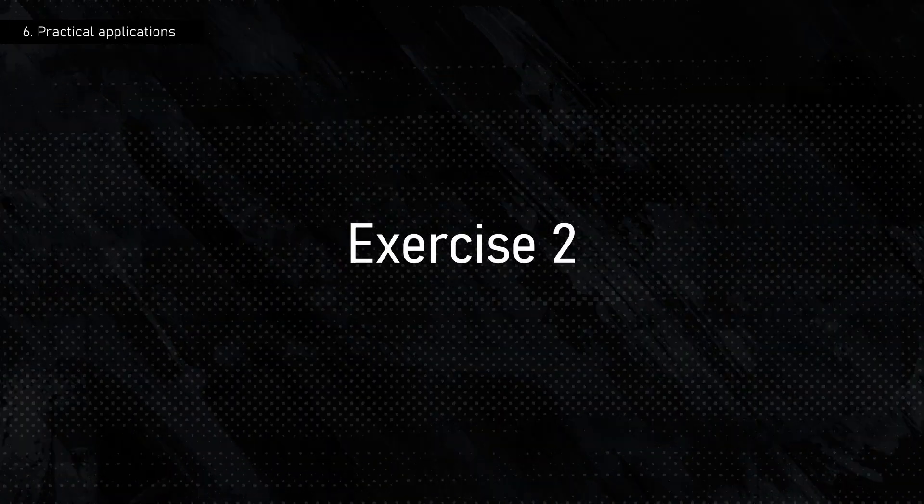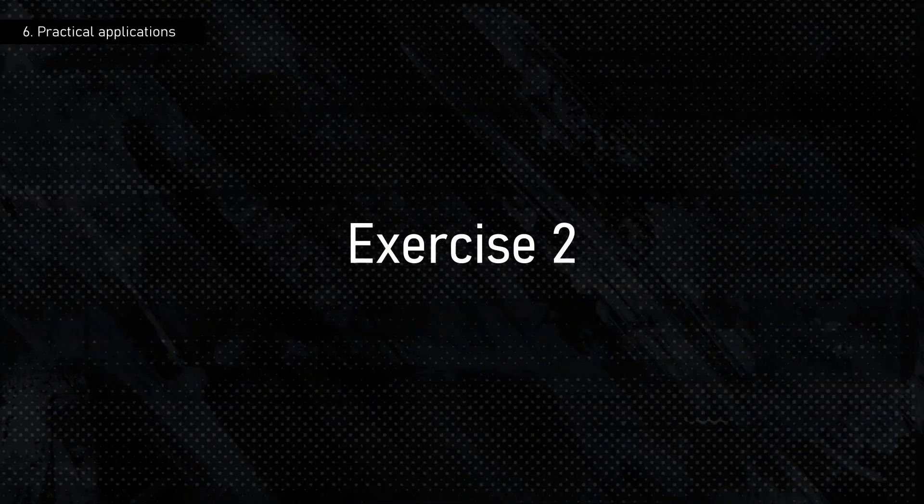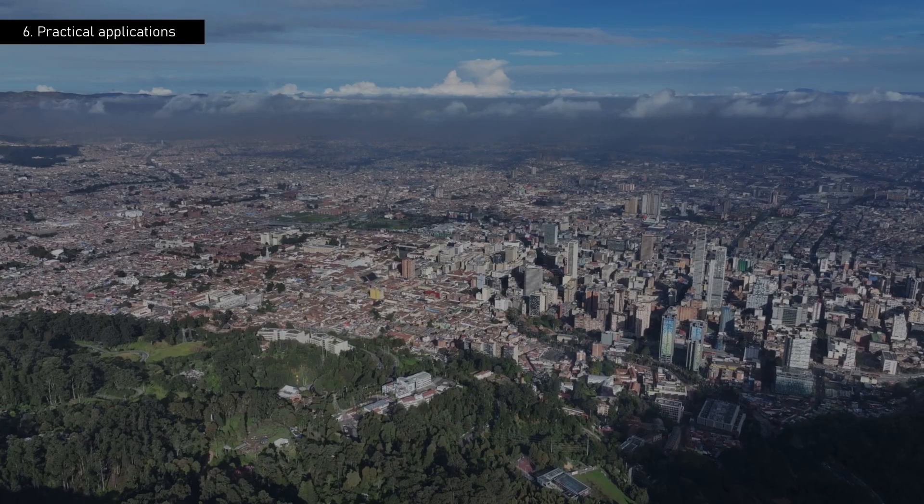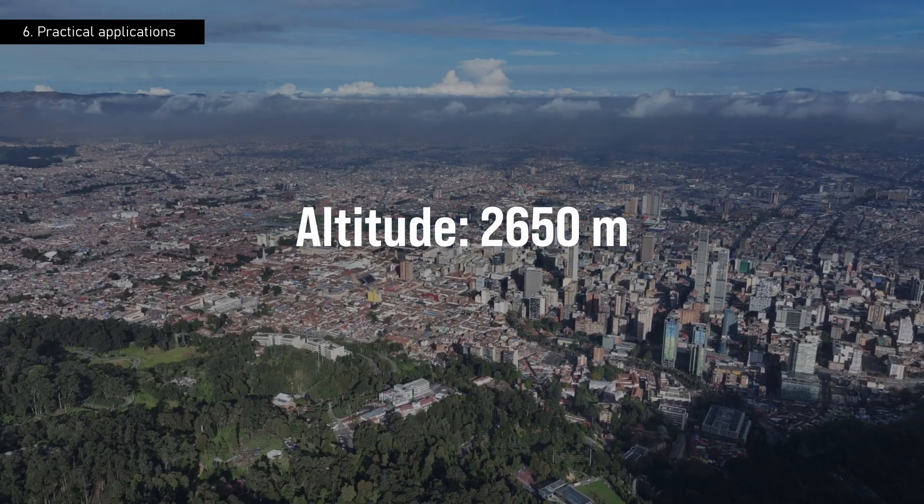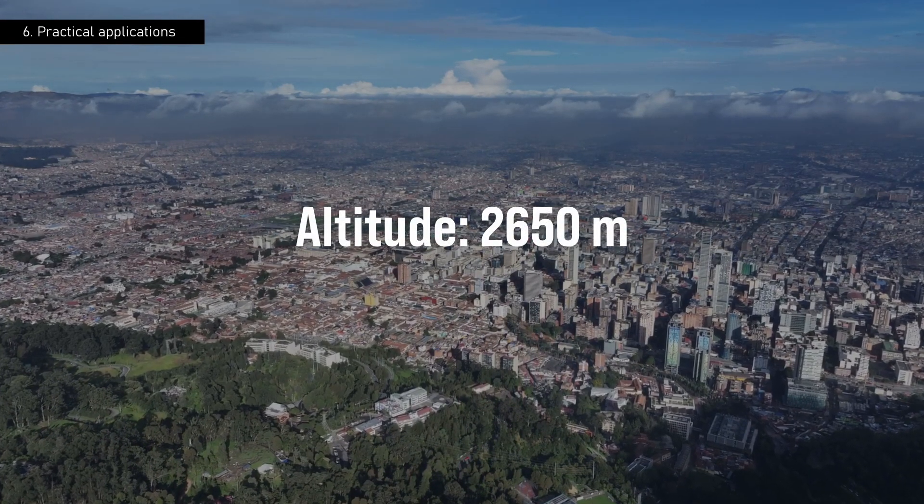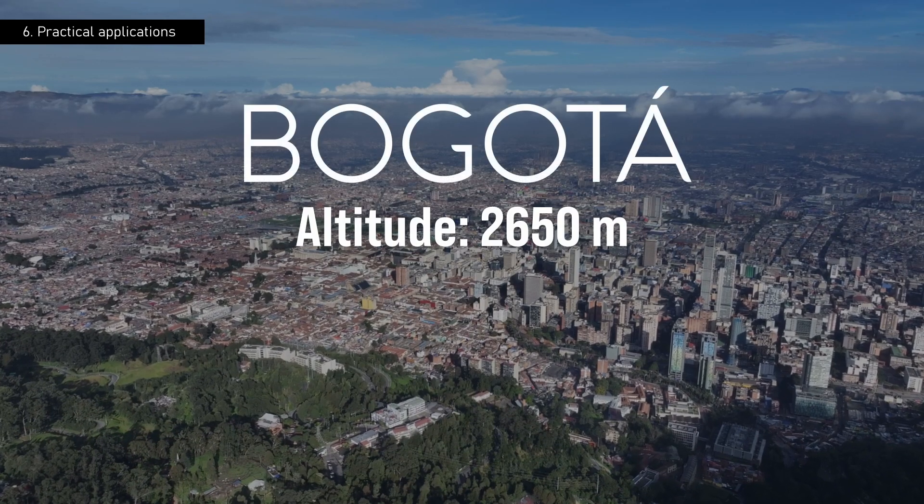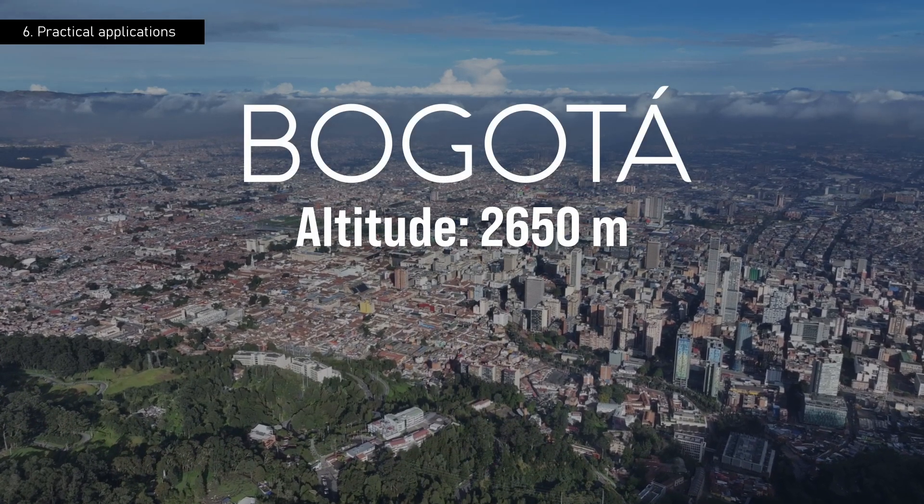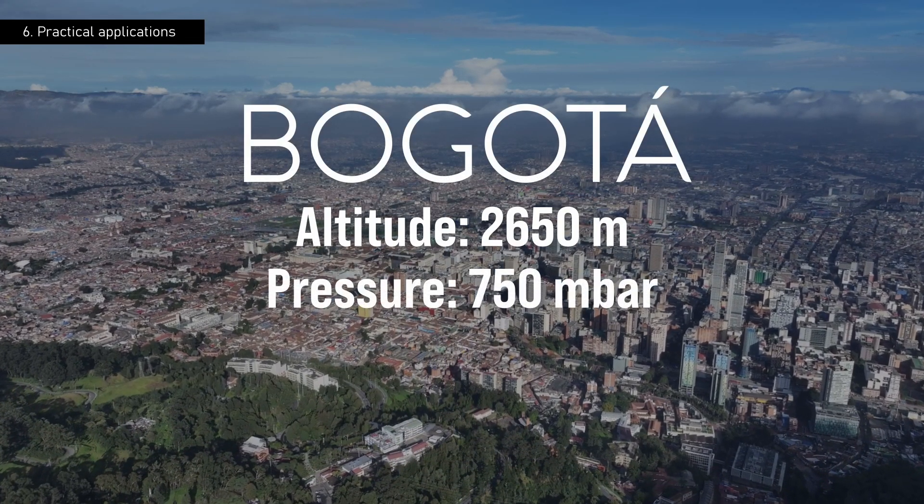Now consider a more specific example, where we calculate the maximum relative pressure of our vacuum pumps located at an altitude of 2,650 meters above sea level in the city of Bogota. Here, the atmospheric pressure is approximately 750 millibars.